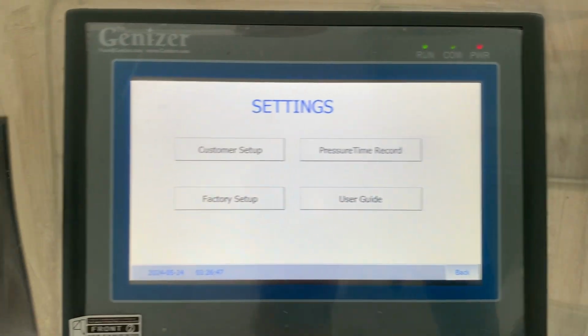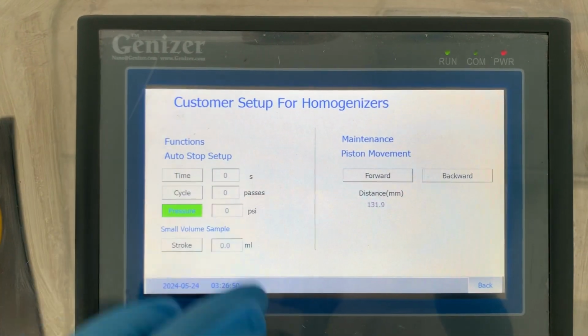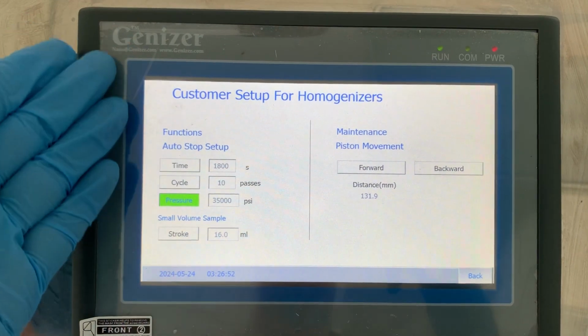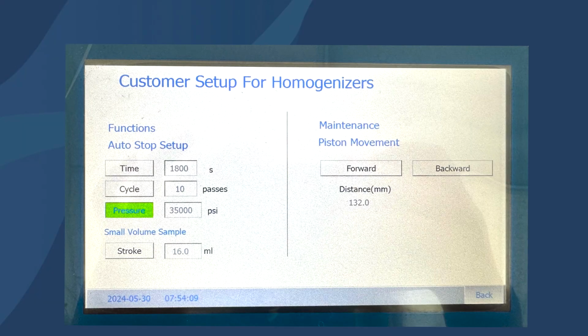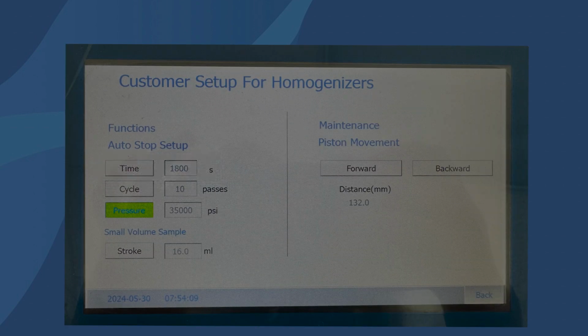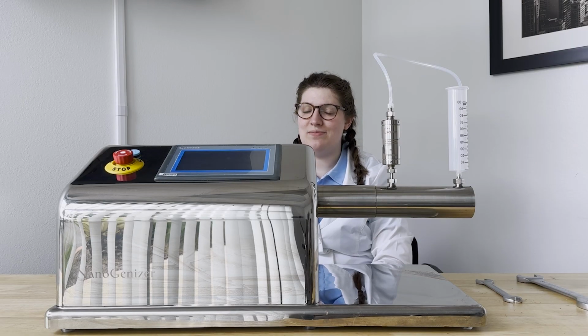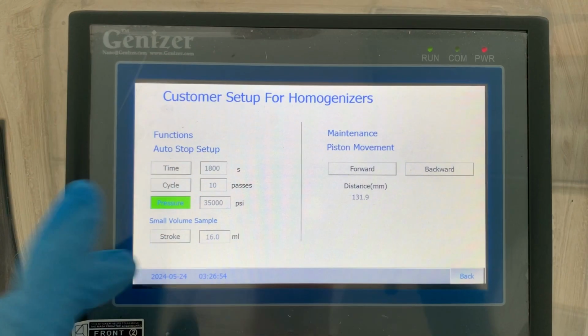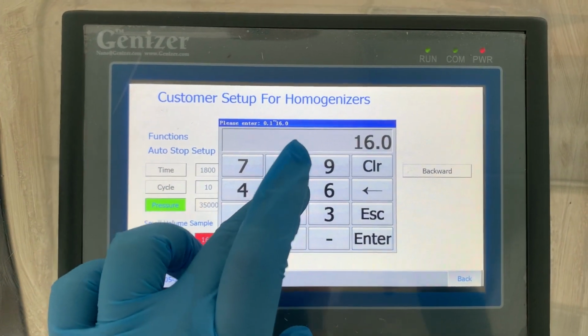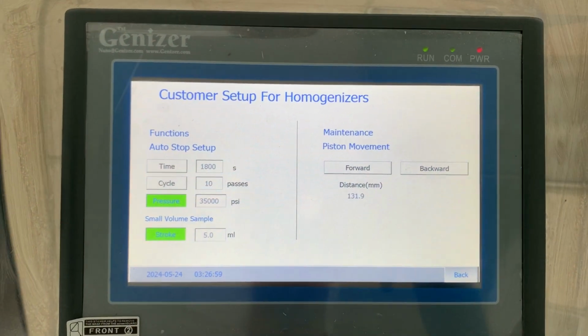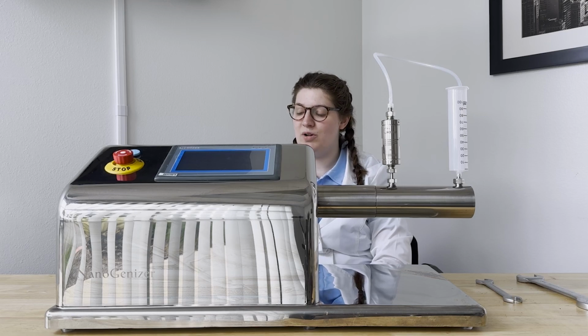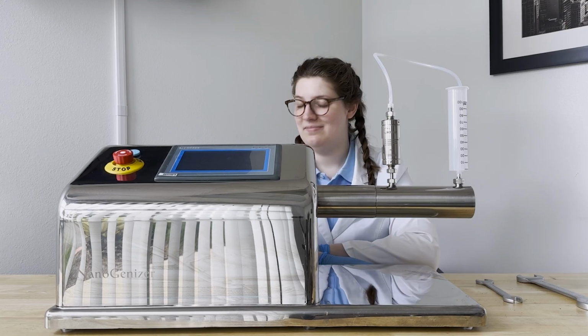In the customer setup menu, you will see many auto stop options. Select them in green for the machine to stop automatically when that condition is reached. For instance, cycles, time processed, or if the machine goes above a desired pressure. These auto stop conditions reset when your machine stops, so make sure to redo them if you want the same conditions for your next run. Small volume sample can be used to adjust the volume taken in by the machine for each pass. This may impact the speed required to get to a desired pressure.